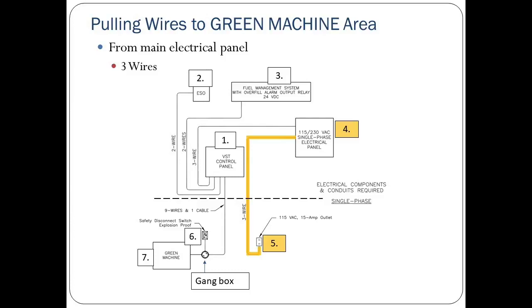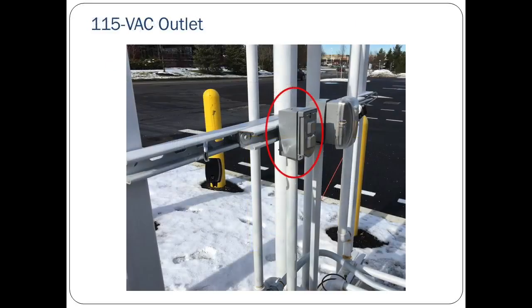The other set of 3 wires that need to be pulled to the Green Machine powers a 115 VAC outlet from the main electrical panel. This outlet is to be installed near the Green Machine and will be used for testing and any maintenance that requires a power source. In a real-life setting, here's what the outlet will look like after it's been installed correctly.